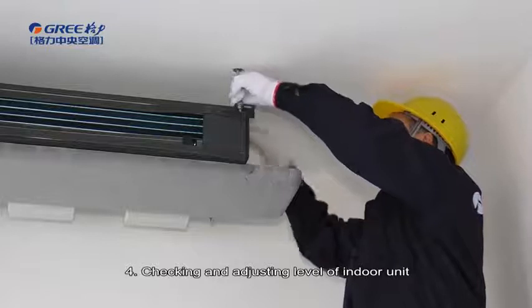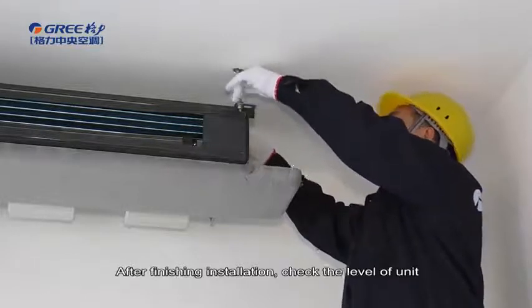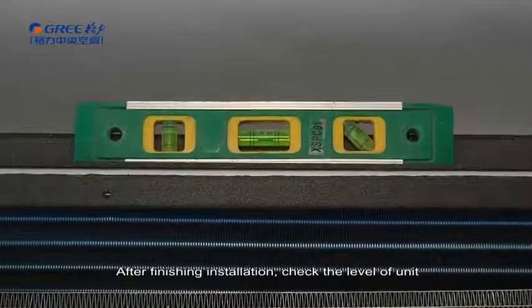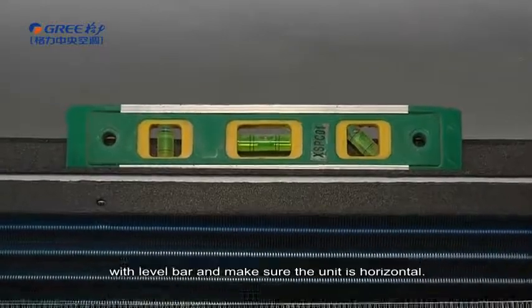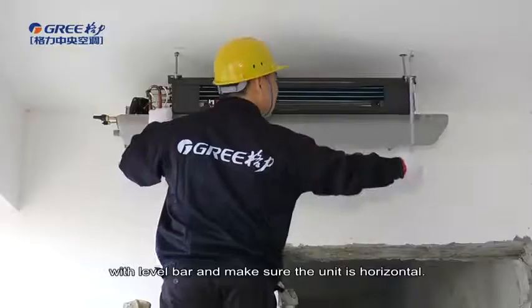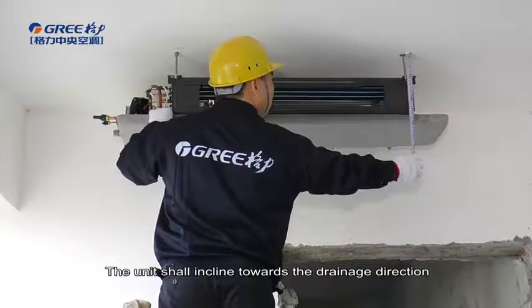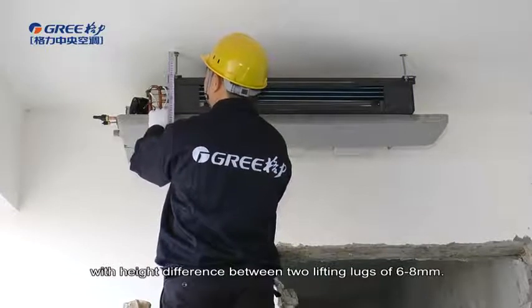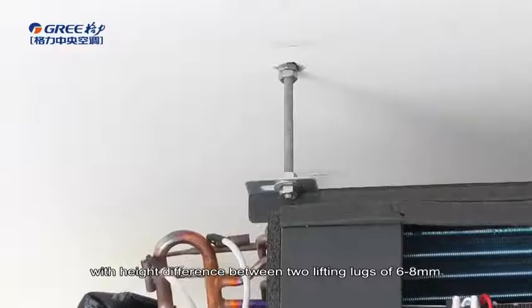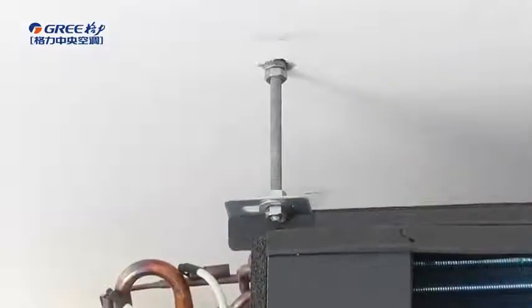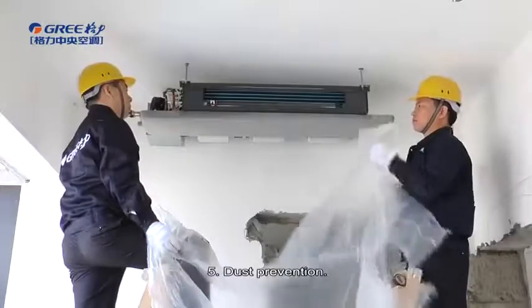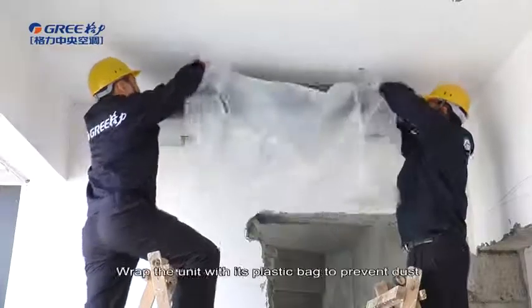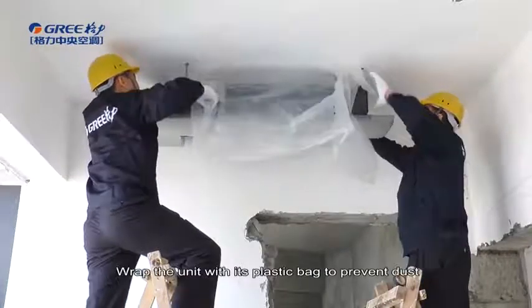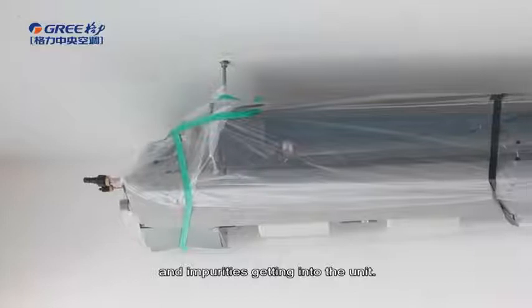Fourth, checking and adjusting level of indoor unit. After finishing installation, check the level of unit with level bar and make sure the unit is horizontal. The unit shall incline towards the drainage direction with height difference between 2 lifting lugs of 6 to 8 mm. Fifth, dust prevention. Wrap the unit with its plastic bag to prevent dust and impurities getting into the unit.